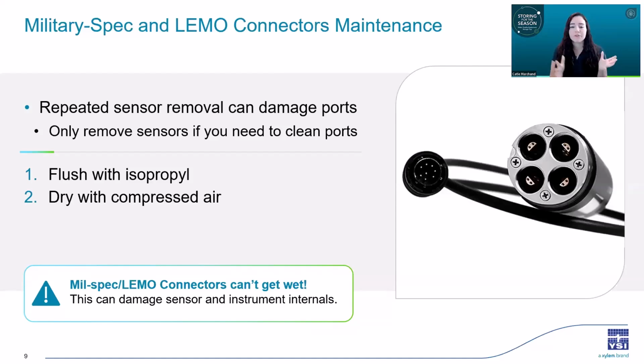So only remove your sensors if you suspect you need to clean the ports, like if you're having issues calibrating or you notice something is off in your data. And of course, if you need to swap sensors. So to clean these ports, you're just going to flush them with isopropyl alcohol and then dry them with a small puff of compressed air. And make sure the ports are completely dry before reinstalling your sensors. You don't want any alcohol or water left in there. It can cause some damage. And also these ports, you do not want to put any grease in them. They do not like grease.